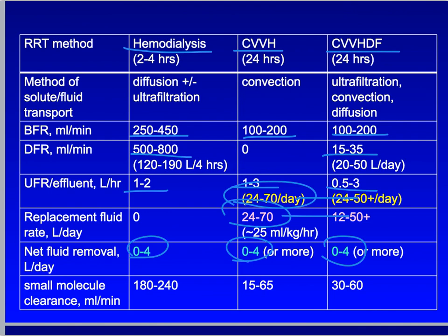Note that the clearances of small molecules in both types of continuous therapy are about the same, even though CVVH uses convection only, while CVVHDF employs convection and diffusion. The reason for the equal clearances is that small molecules diffuse readily across the membrane so that they are very efficiently removed by either dialysis with diffusion or CVVH with convection.